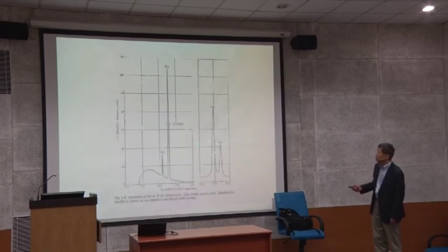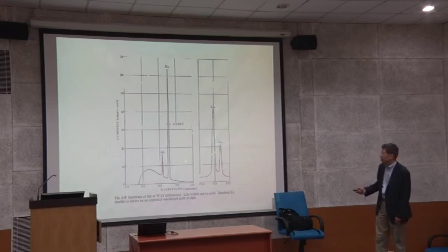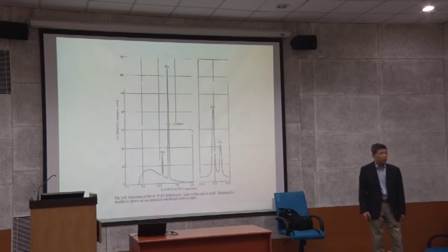So when you look at the K alpha line, you can see K alpha 1 and K alpha 2; these are two different energies, and this intensity is stronger than this. Usually you can easily cut the K beta line using a filter. Use a filter material that is one atomic number smaller than your anode material.